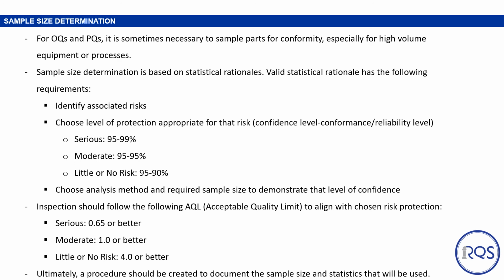Inspection should follow an acceptable quality limit or AQL in order to align with the chosen risk protection. With serious, typically an AQL of 0.65 or better is required. For moderate, an AQL of 1.0 or better is required. And for little or no risk, an AQL of 4.0 or better would be required. Ultimately, all of this information should be documented in a sample size or statistical procedure, and this also should be documented in any associated validation plans or protocols.